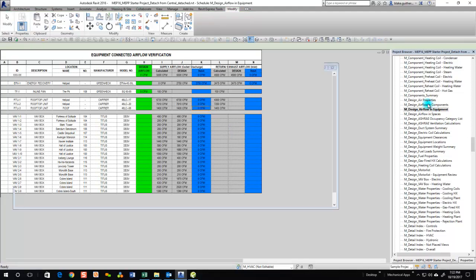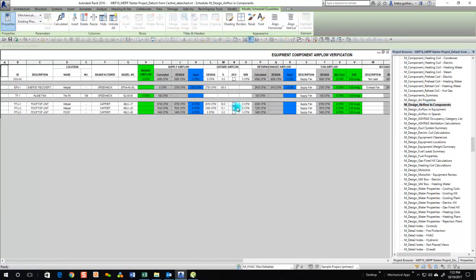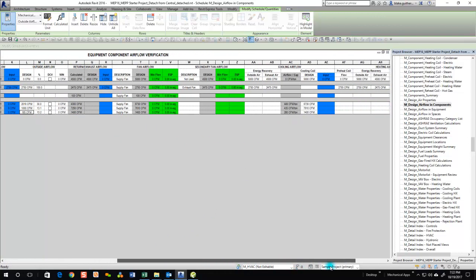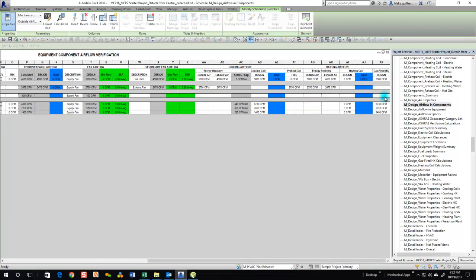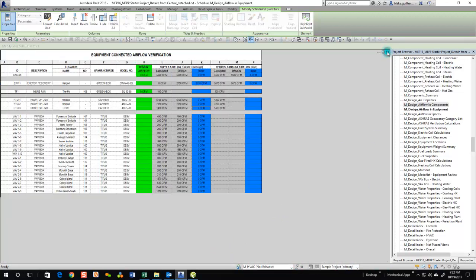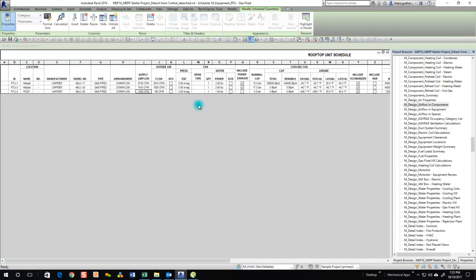Airflow in components now is a place where we could edit the outside air value. I believe we needed 180 CFM, 185 for this unit, not that much. So that's 13% of our airflow. You'll see the gas-fired heat exchanger is using that airflow as well. Okay, so now back in this schedule, there's just a few things left to update. We could update our external static pressure. This is going to be very minimal. So let's go 0.5.